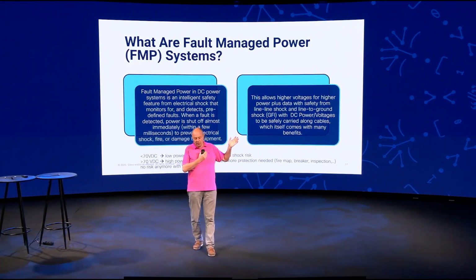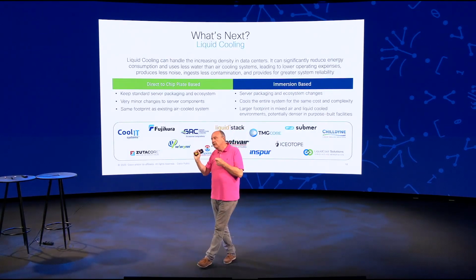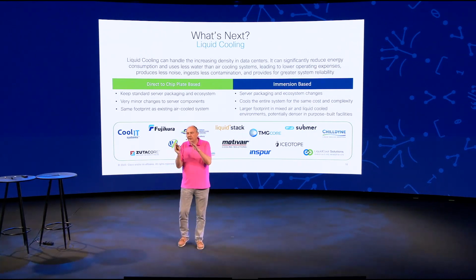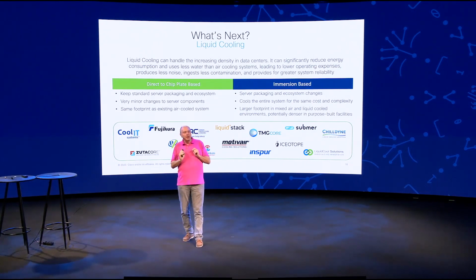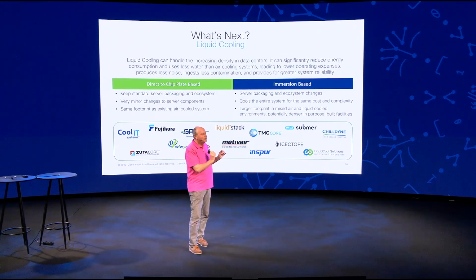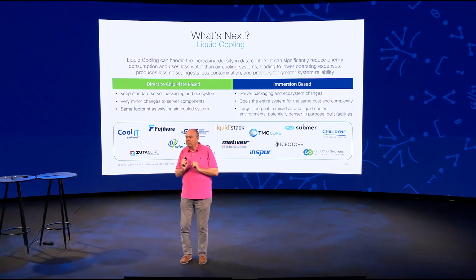That's why you have a new technology emerging called fault-managed power, which injects data information into your power cable to detect when there's a short circuit or a shock or anything that has to do with safety. By integrating this digital electricity, if you like, inside the power cable, we could now provide the same level of safety as with 48 volts, but running at 380 volts or 600 volts if you want.